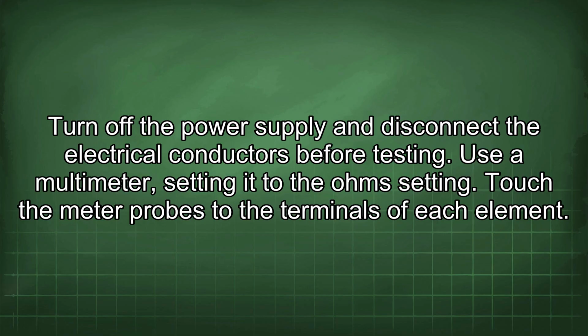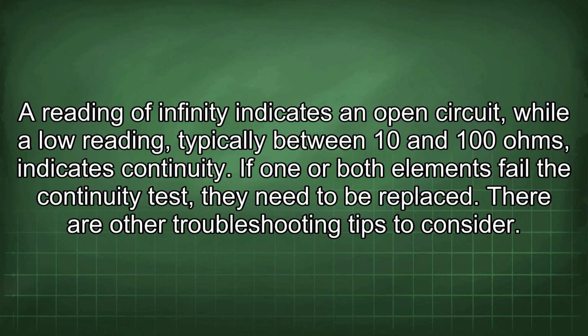Use a multimeter, setting it to the ohm setting. Touch the meter probes to the terminals of each element. A reading of infinity indicates an open circuit, while a low reading, typically between 10 and 100 ohms, indicates continuity. If one or both elements fail the continuity test, they need to be replaced.